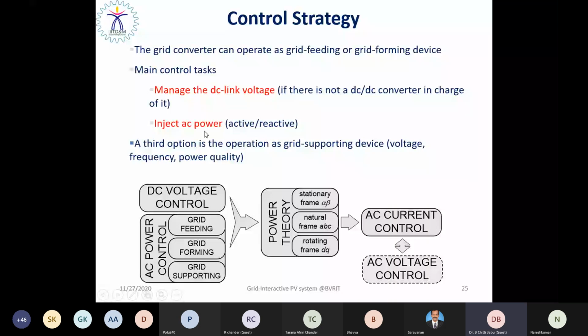And the third option, maybe it acts as a grid supporting device, as it can provide ancillary services like voltage control, frequency control, and power quality, right? So the AC power control includes grid feeding, grid forming, and grid supporting, and on the grid side, it has AC current control and AC voltage control. And on the input side, it has a DC voltage control, right?